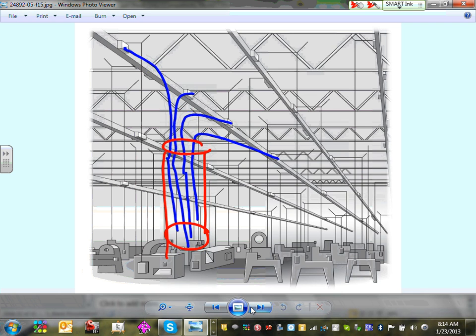Any comments, any questions about trolley busways? Would that make it more expensive? Not really. That's aftermath. It used to be when we went there, each one of them was coming like this, but then you look into it and you can't see anything. It's all cables coming all the way down, looks ugly. So they just grouped them together, and I'm sure they have to buy this one. It adds some expense. The question would be, do they have to derate? Depending on what type of sleeve they put here. If it's a conduit, then now you're bringing multiple cables carrying current, you have to derate. I don't think it was a conduit, some type of sleeve that they put on them just to group them together. Yeah.